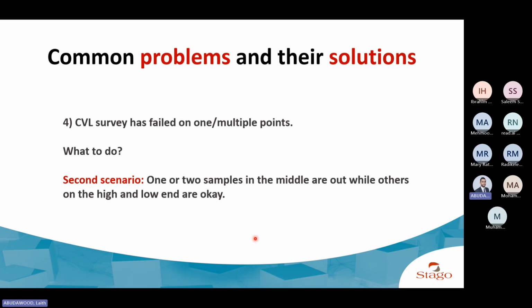So what do I do? Again, we can use our own samples to verify the linearity. If you have this issue, we can discuss exactly what protocol you can use. There are different ways to check this. The second important thing that you need to check is whether these materials are deteriorated, because results failing in the middle concentrations is not normal. So it's very important for you to verify the stability of the materials. Were they thawed when I received them? Were they prepared correctly? Were they run correctly?